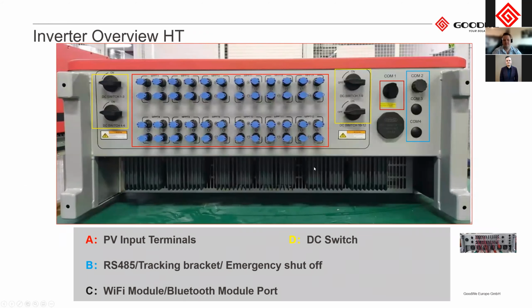Then we have the HT inverter. As you'll see, this is much larger than the MT series. From the 110 and 120 kilowatt, we'll have 12 MPPTs. As you'll see, we have DC switches here below. The DC switches are a multiple of the MPPTs, so each DC switch covers 3 MPPTs. As you'll note here, DC switch 7 to 9, DC switch 10 to 12. So the 3 MPPTs are isolated by each DC switch.